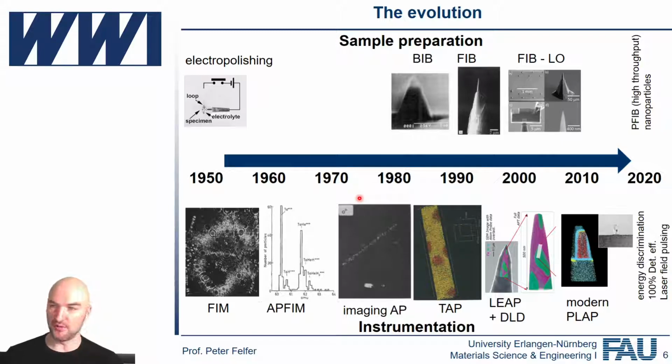A very trivial thing can be that I've very often seen people find older, not even that old, papers about pulsed laser atom probe, where it says, okay, we did our experiment with pulse energy X and temperature Y, and they don't. When you haven't done that before, you might not know that pulse energy is completely not transferable onto the instrument that you're using currently.